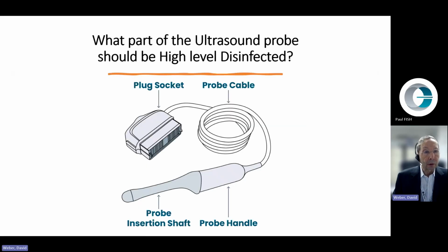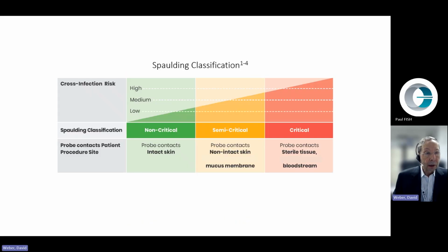So what part of the ultrasound probe should be high-level disinfected? Well, we have the probe, the insertion shaft, we have the probe handle, we have the probe cable, which then leads to a plug socket, obviously, to provide electricity for the probe. Here is the Spaulding classification. This has been used now for decades. It's widely accepted around the world. It looks at the risk of infection based on how a medical device is used.